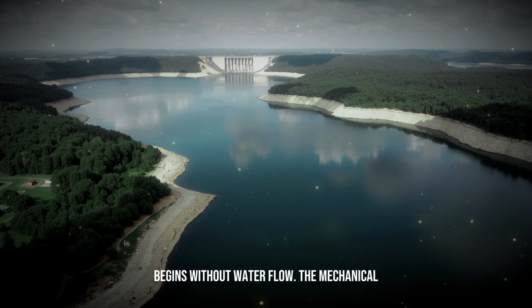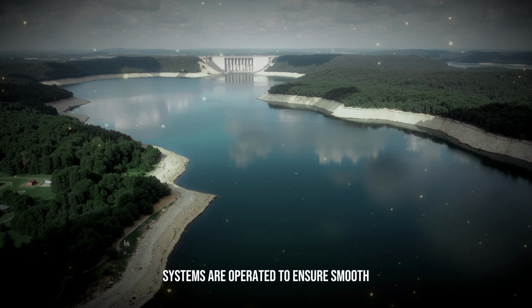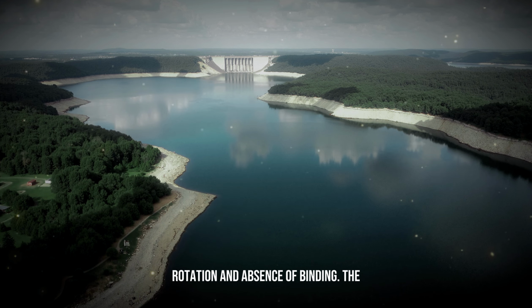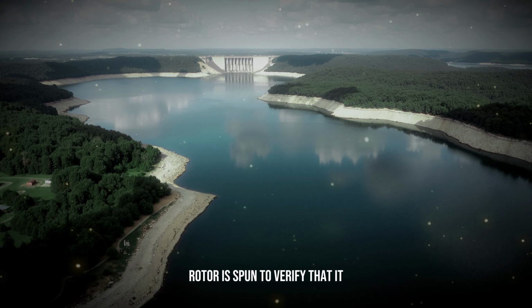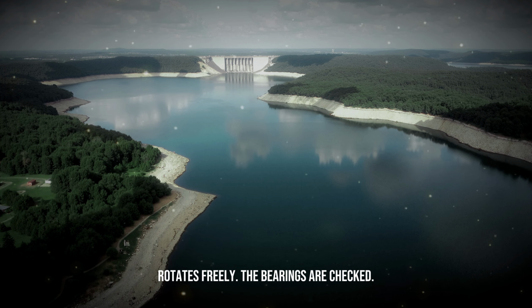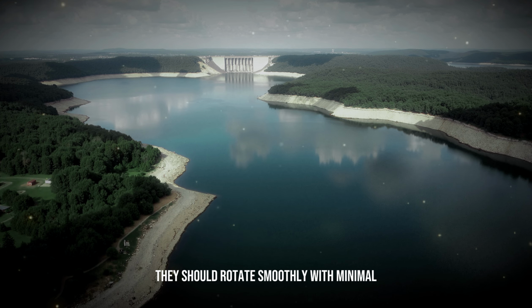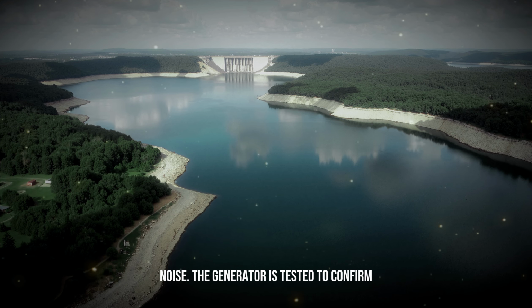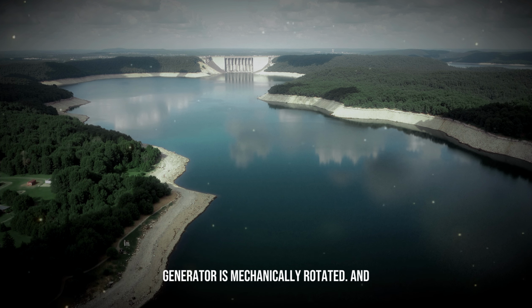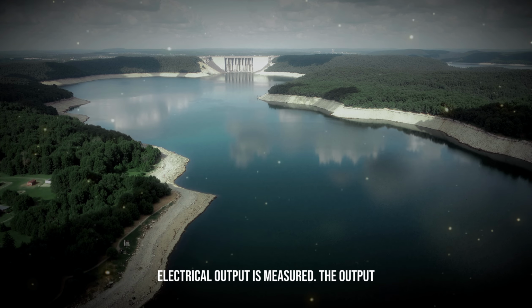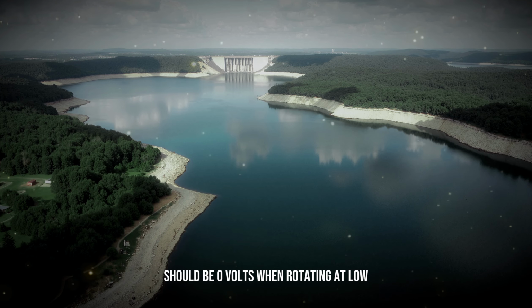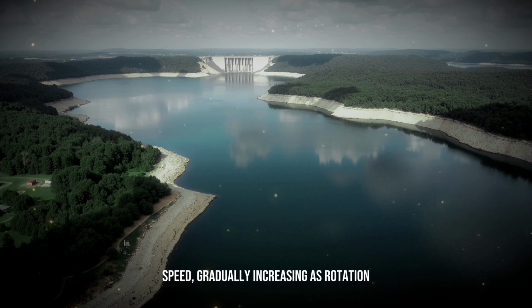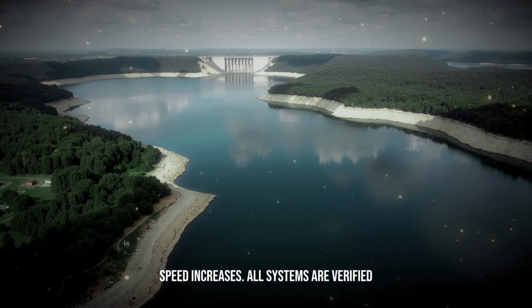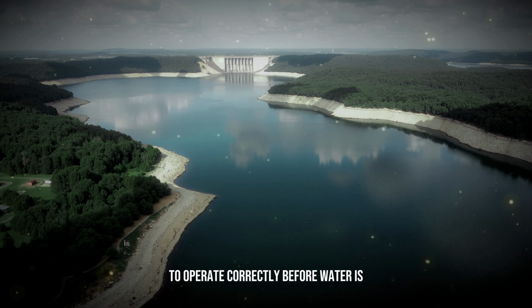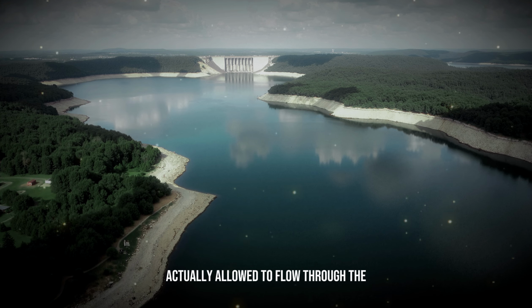Testing of turbine systems begins without water flow. The mechanical systems are operated to ensure smooth rotation and absence of binding. The rotor is spun to verify that it rotates freely. The bearings are checked. They should rotate smoothly with minimal noise. The generator is tested to confirm proper electrical generation. The generator is mechanically rotated, and electrical output is measured. The output should be 0 volts when rotating at low speed, gradually increasing as rotation speed increases. All systems are verified to operate correctly before water is actually allowed to flow through the turbines.